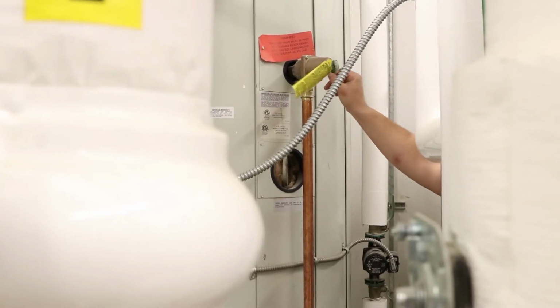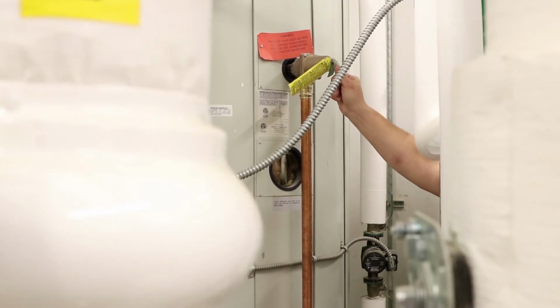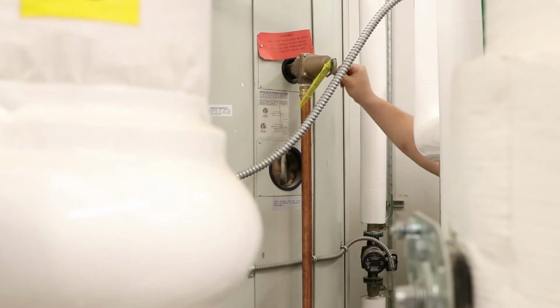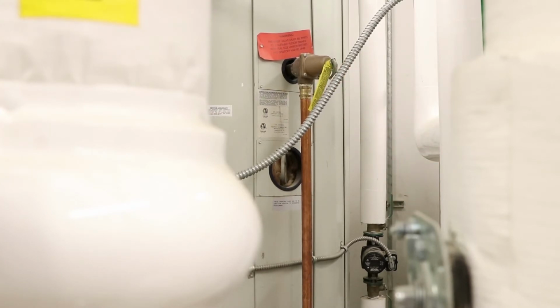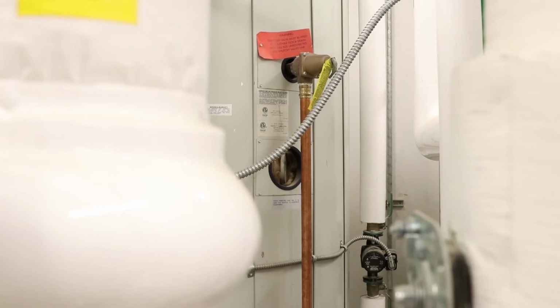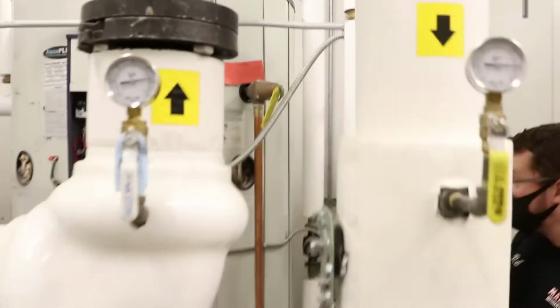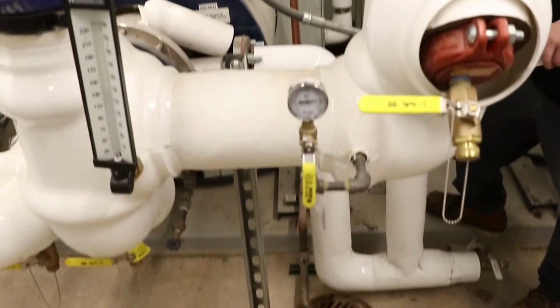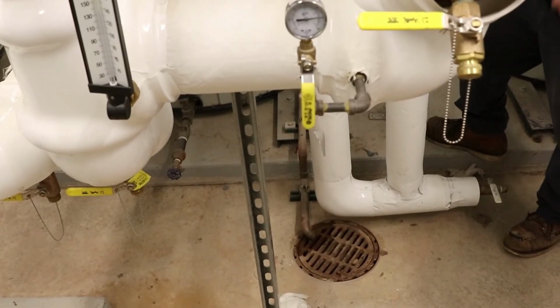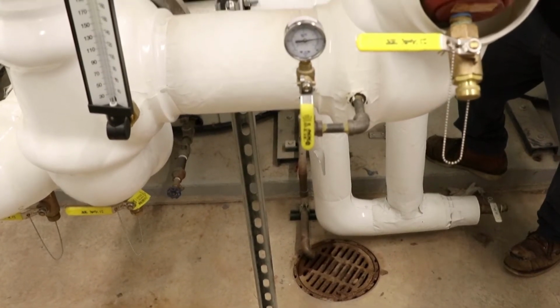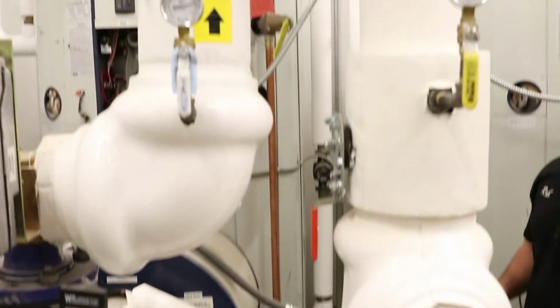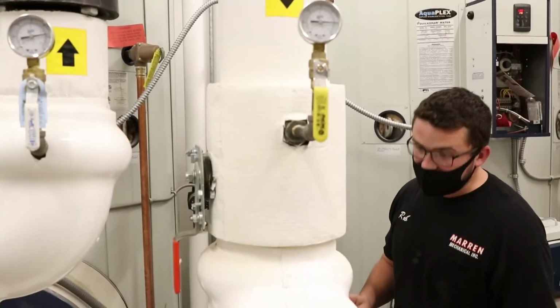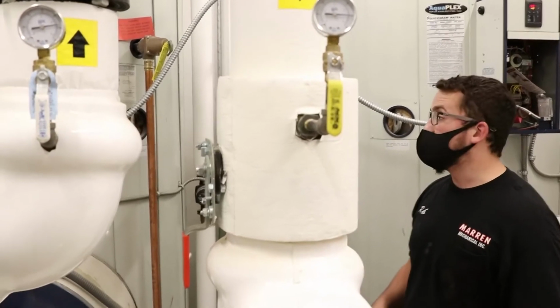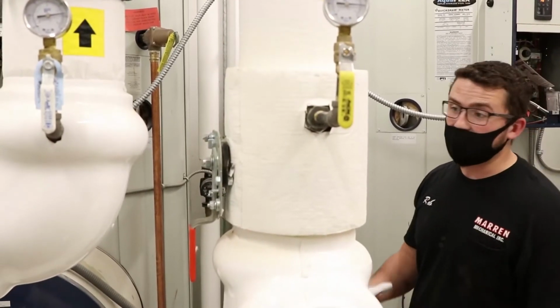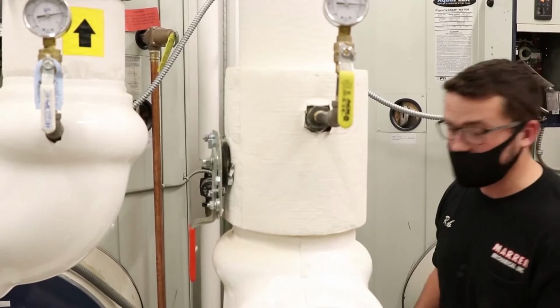You'll gently lift up on this lever. You'll hear water begin to come out, and you'll get some discharge out of the pipe on the floor. You release the lever, and it should stop. It's very important that water comes out of that drain when you lift the lever, and it's also very important that water stops coming out of that drain as soon as you release the lever. If you're not able to get water to discharge out of that drain by lifting the lever, the relief valve needs to be replaced. If the water does not stop coming out of that drain after you let go of the lever, the relief valve needs to be replaced. Either of those instances, you should call for service.